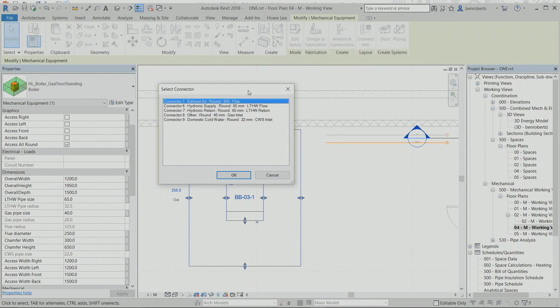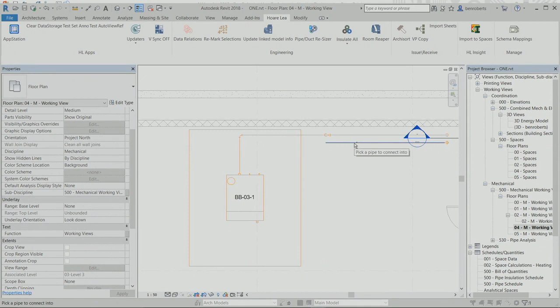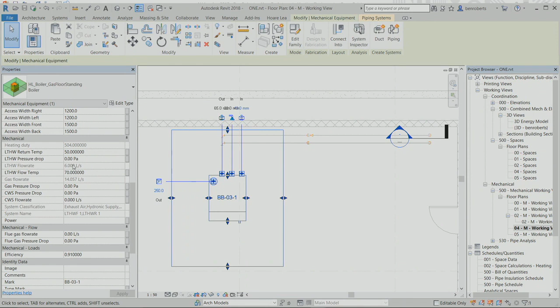And this time I'm just going to do this, Connect Into. So you select a piece of equipment, you click Connect Into, you choose which connector you want to go from, in this case the LTHW flow, and in this case LTHW return, and then select the return pipe, and it will connect them up. So we've now picked up a flow rate in the boiler, LTHW flow rate 6 litres a second. We've got an LTHW flow and return temperature, which in turn gives us a heating duty.